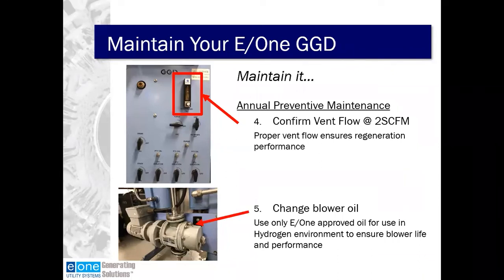During your daily checks of the unit, most times you'll see no gas flowing in this flow meter. That does not mean you go over and open the valve fully. That means the unit's not in regeneration mode at that time. So this step is performed during the annual maintenance procedure. It ensures that the regeneration is performed properly with adequate flow. But once we do that, there's no reason to change the flow meter setting.